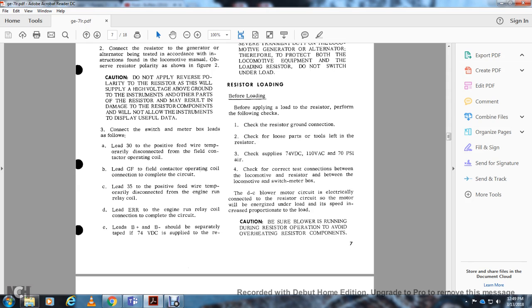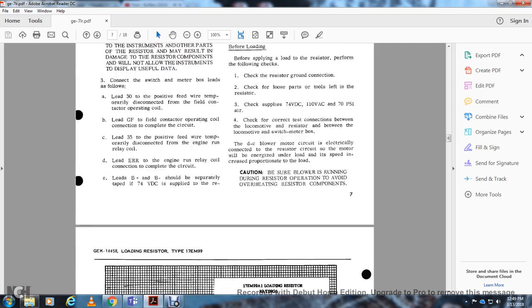The DC blower motor circuit is electrically connected to the resistor circuit, so that the motor will be energized under load and the speed increases proportionately to the load. Caution. Be sure that the blower is running during resistor operation to avoid overheating the resistor components.